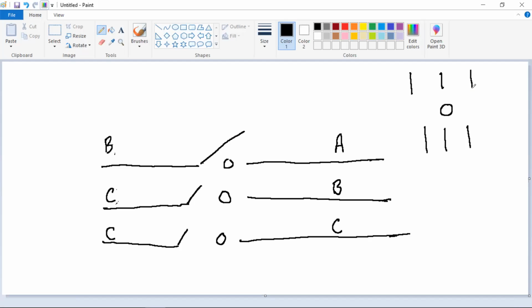All right. In normal operation, before I install my switch, this was like this, right? Here's my cross arm. Okay, so all my phases really were all the same phase to start with. This was A, this was B, and this was C. As soon as I install my switch and dead end this side, dead end this side, and this side, and put my jumpers to the switch, am I worried about phasing?